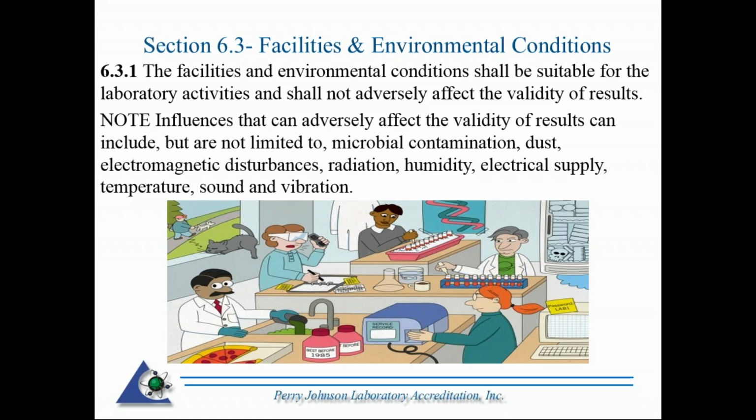The cartoon picture depicts things that may warrant not fulfilling the requirements stated in 6.3.1. Incompatible activities, perhaps you have sensitive equipment nearby an area which is producing vibration, are an example of conditions which would adversely affect the tests or calibrations being undertaken.